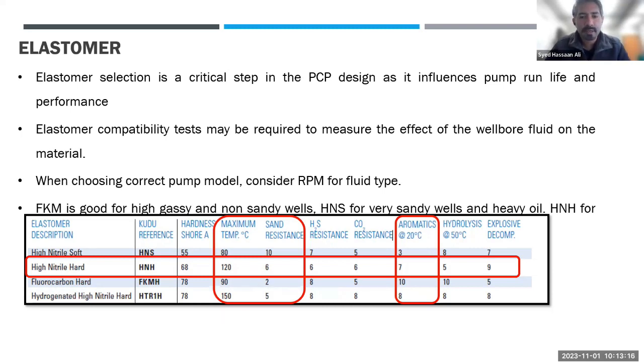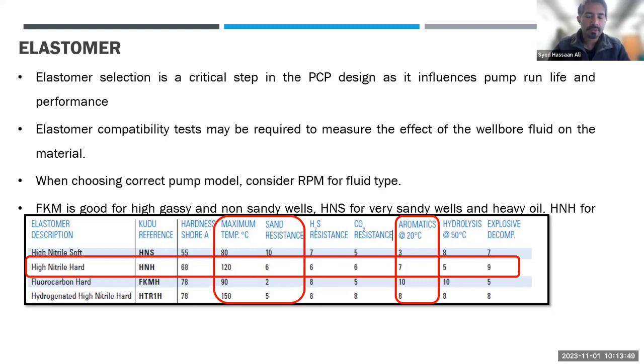One key thing about the elastomer is that once it comes in contact with well fluid, it will expand. The interference between the elastomer and the rotor will increase. If you select the elastomer incorrectly and it expands too much, there's a possibility the pump will start losing efficiency due to excessive interference between the elastomer and the rotor. Field by field, your elastomer selection will differ. For mature fields, there is very good performance data on which elastomer will work with their specific reservoir fluid. The elastomer forms the core of the PCP system.